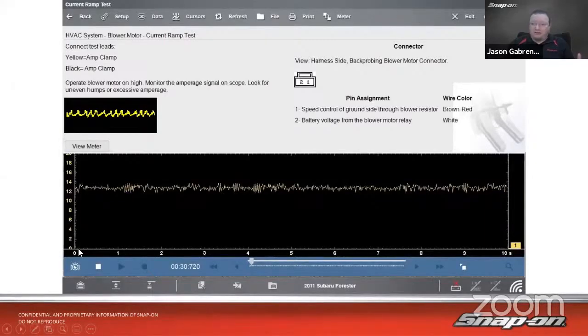Now this is also looking at a graphing meter at a 10-second scale is what this pulls up for us. So we want to make sure it's not too high of an amperage. Usually on high, you don't want to see more than say 15 or 18 amps, depending on the circuit size. Oftentimes the manufacturer will publish that. So you just want to make sure it doesn't exceed that. You want to make sure it doesn't have any dropouts or weird things going on.